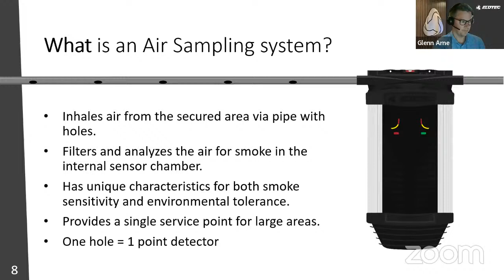And where should I use the aspiration detector? It's very good to use in large rooms that require high sensitivity, and in difficult environments where point detectors are unsuitable, for example cold storages, freezing rooms, heavy industry, etc. And for highly sensitive detection in special environments like computer rooms, where you want early detection. And it can also very often be a very affordable alternative to point detectors. In some cases, if you have very big areas, maybe you need several hundred point detectors. Instead, you can replace that with a small number of aspiration detectors. And also, you don't have to climb all the way up to the ceiling using a lift. You have the service point easily placed on the wall, where you do both the commissioning and the service.